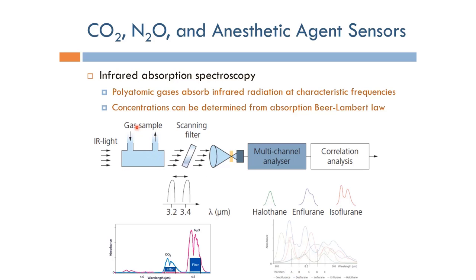The infrared absorption spectroscopy system consists of an infrared light lamp, and we enter the gas sample through a transparent quartz lens. We have a scanning filter that chooses which bandwidth we are going to use in measurement, focusing lenses, and a detector. We can sometimes use a multi-channel analyzer to compute all of them at the same time, and then use the Beer-Lambert Law to compute the concentration of each one.